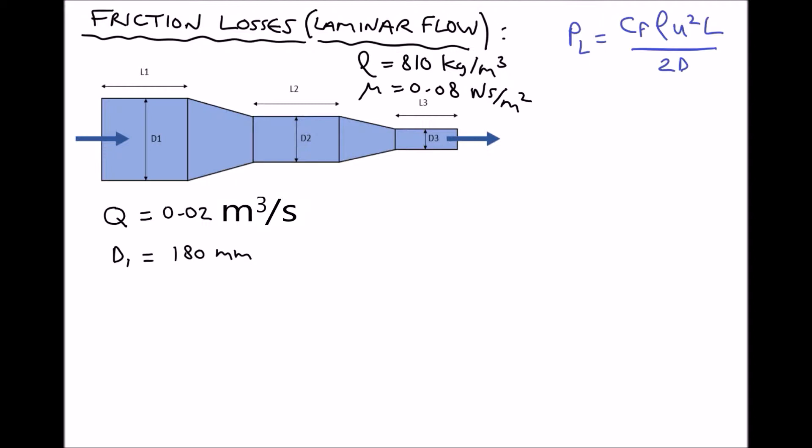There's only one equation that we need to calculate pressure losses due to friction and it's displayed in the top right hand corner. Pressure loss equals Cf — C subscript f is something called a friction factor. Rho is the density, U squared is the fluid velocity squared, L is the length of pipe divided by 2 times the diameter. So there's quite a lot of factors that affect the amount of pressure that's going to be lost as a result of friction.